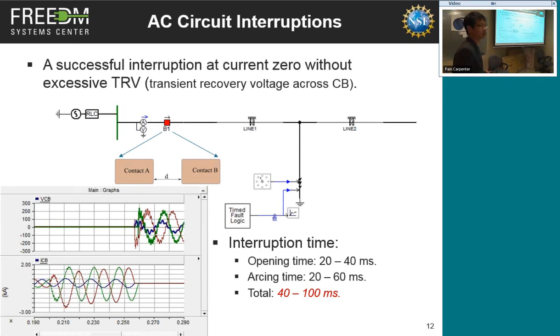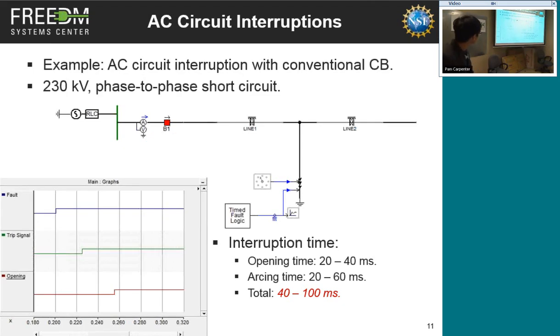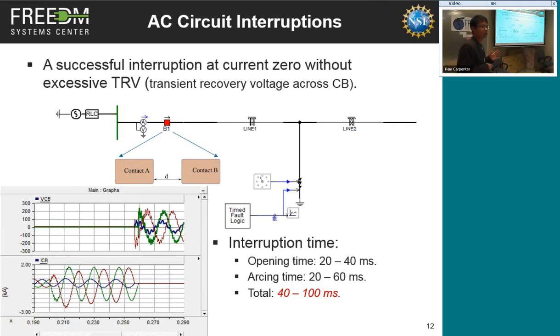Well, ideally you hope that, okay, I open this contact, the circuit is interrupted, nothing happens, that's all. But that's not the case. What really happens there is, if we look at this sequence, this moment is the actual opening moment for the contact to initially part. So at that moment, there's a very finite opening between the contacts. And what happens then is there will be an arc. The current will try to flow if you are not strong enough to actually break the circuit. So the arc will continue flowing until some conditions are met.